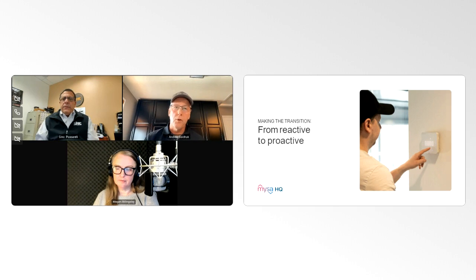Definitely, as you build out your portfolio and you have thousands of thermostats connected online, you want to be alerted when there is going to be an issue. Having those real-time alerts helps you narrow down and take proactive measures. And you can see at that point whether you are getting temperature swings or it's not meeting set points. And what I also mention to facility managers is that the data we see in the runtime reports are insights you can share with the technician as well. I know if I'm going on site and I get that extra bit of intelligence, knowing what is happening, as a technician that's going to allow me to narrow down what the potential problem is with the HVAC system.